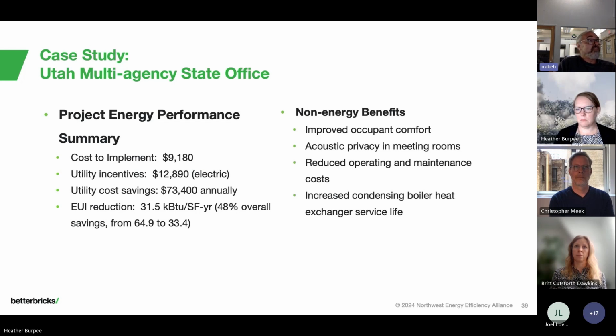Total utility cost savings were $73,400, making the return on investment instantaneous. Our EUI reduction—since EUIs are of interest in many of these building retrofit projects—was 31.5 kBtu per square foot, a 48% overall reduction. Our starting EUI was 64.9, and our ending EUI was 33.4. Interestingly, energy modeling done as part of the high performance building design standards predicted an EUI of 36. So the model was right, the operations were wrong in this building, and got corrected.